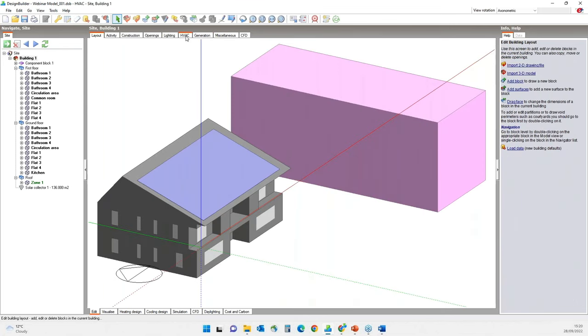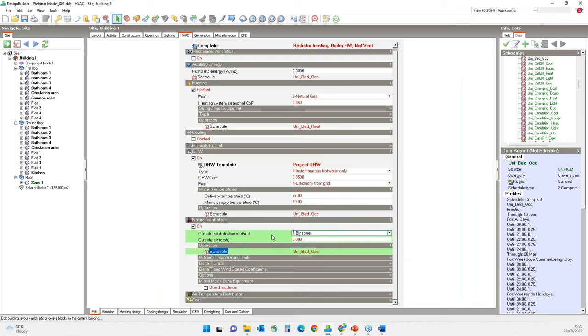Moving on to the HVAC tab, you will immediately notice that unlike the scheduled option, some inputs under the natural ventilation header have a green background. This is because when the calculated option is selected, ventilation rates are calculated using wind and buoyancy driven pressures, opening sizes, operation and fabric infiltration details — not predefined airflow rates. The inputs with a green background only affect heating and cooling design calculations and not calculated natural ventilation simulation, so these can be ignored here, but you must check them if running a design calculation.